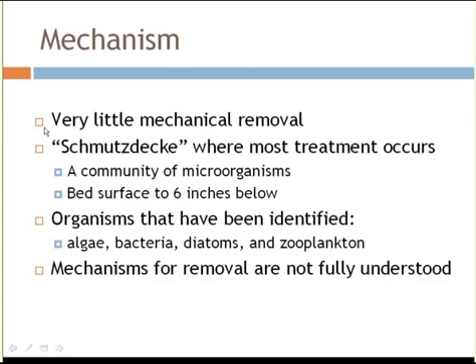Since this is a biological system, there is actually very little mechanical removal, although some does occur. The sand itself is a matrix on which a community of microorganisms grow, specifically at the surface of the sand bed. After a time, the surface becomes slimy, and the term associated with that slime film is schmutzdecke — that's where most of the biological treatment occurs. The treatment capacity does continue down into the sand bed, down to about six inches below the surface.